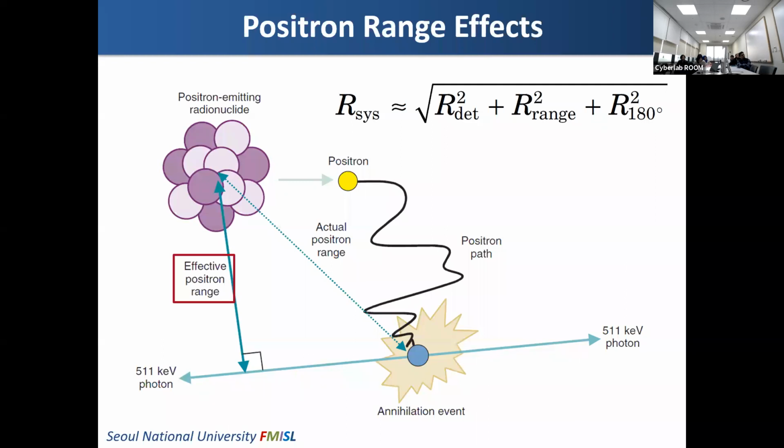If we don't have a collimator and some event is detected, we cannot say what the direction was. That is why we use a collimator to reject these lines. But in PET, because we detect two photons, we know what the direction was.